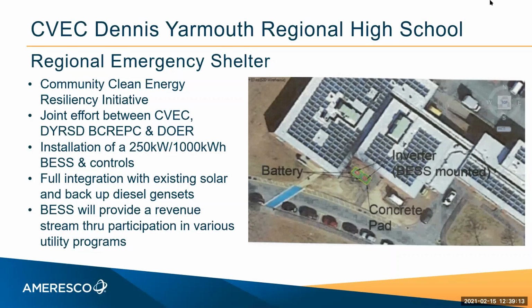Yeah, I think that's right. It's more of a safety issue, Brian, as you point out. You have to isolate the facility from the grid, because the grid operator, whether it be Eversource or National Grid or some muni, has as its biggest concern that when they send somebody up on the pole, that person isn't injured by something backfeeding out through the grid. Unless there was some special switchgear or dedicated line adjacent to the facility, and even then that's somewhat problematic because the franchised rights of way become problematic.